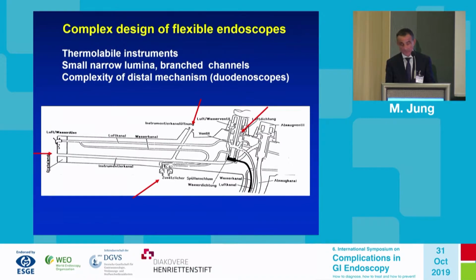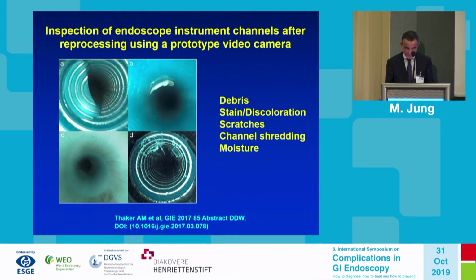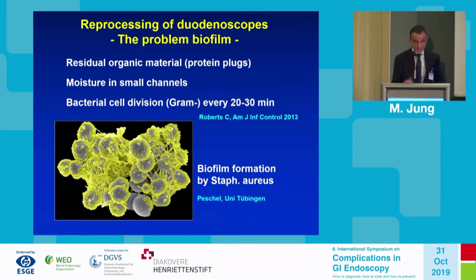And we have the complex design of flexible endoscopes, with small, narrow lumina where we don't have a regular look in, and the complexity, in addition, of the distal mechanism. So 2 years ago at the DDW, an American group presented for the first time an insight into the small lumina with a prototype video camera. And independent of a new or old instrument, they found debris, stain discoloration, scratches, channel shredding, moisture, everything. So the internal part of these channels is not even. In contrast, it gives rise to harboring germs in the scratches and crevices. And this is the case with the problem of biofilm.